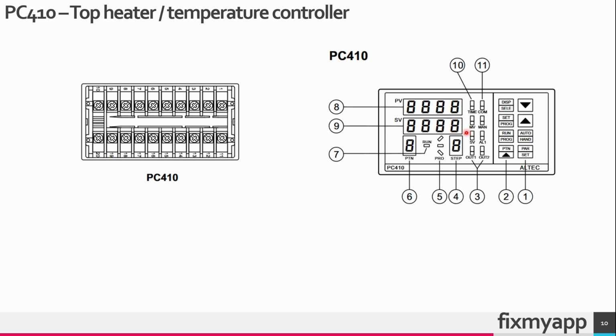The PC410 temperature control consists of a control unit, a temperature sensor such as a thermocouple, and output relays or switches for controlling the heating and cooling elements. It allows users to set a desired temperature set point and maintain the actual temperature close to this set point by adjusting the output to the heating or cooling device.